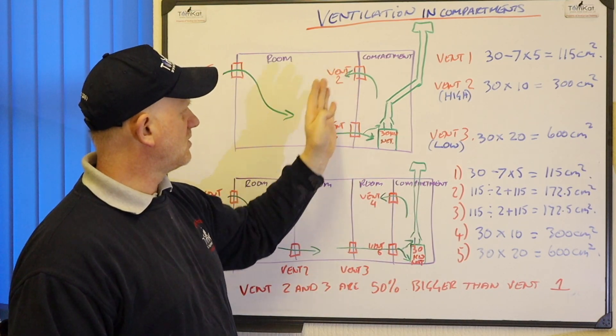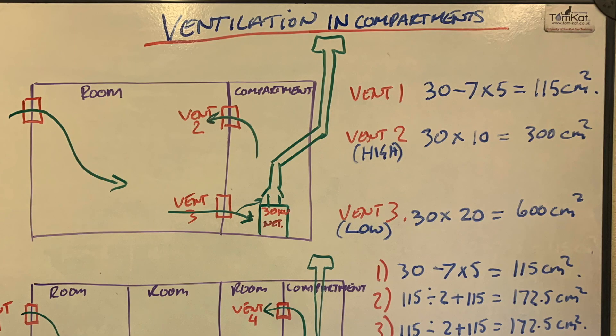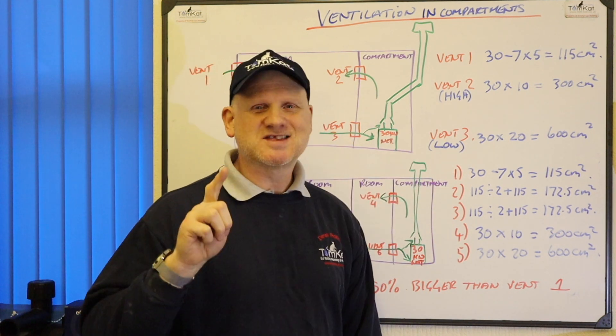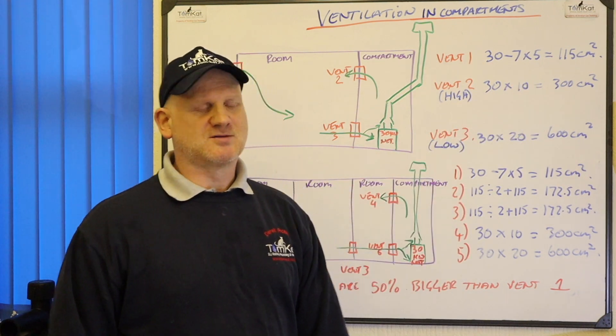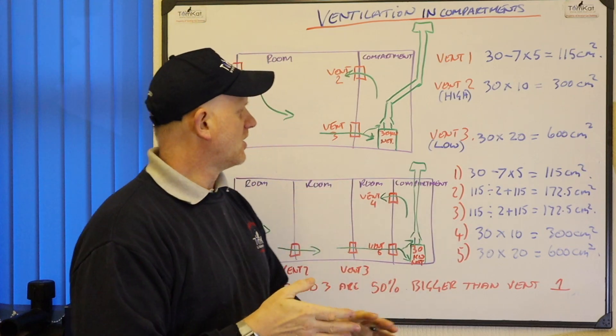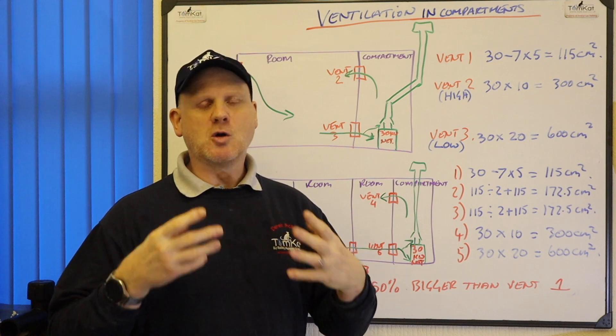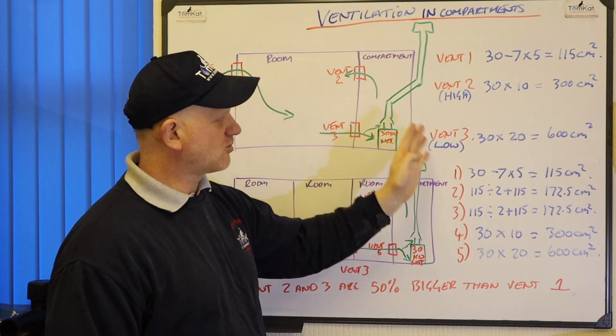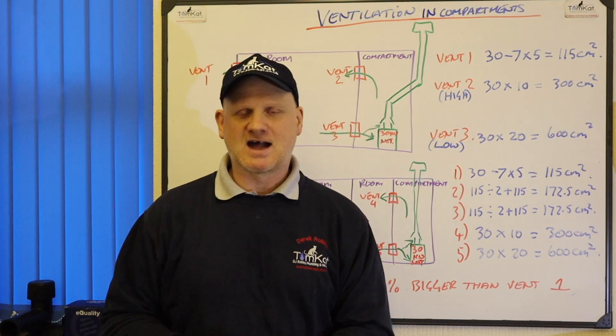When it comes to vents 2 and 3, so vent 2 is a high level vent, remember we don't minus the 7 and this figure is already a net figure so we don't need to divide by 1.11. So vent 2 is 30 times 10 which is 300cm² and the bottom one is 30 times 20 which is 600cm². So there, a couple of big holes. So that's in a nutshell ventilation for an open flue boiler in a compartment. We need to times the kilowatts net by 20 for low level vent and 10 for the high level vent.